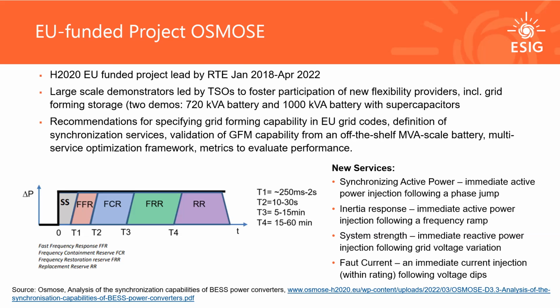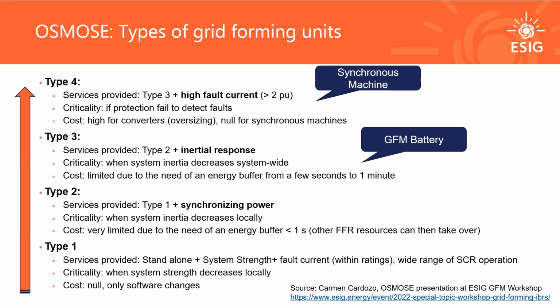And then they identified the stability synchronization services that grid forming inverters can provide. This again includes synchronizing active power, which is what was called phase jump power in National Grid requirements, inertial response, system strength, and fault current.